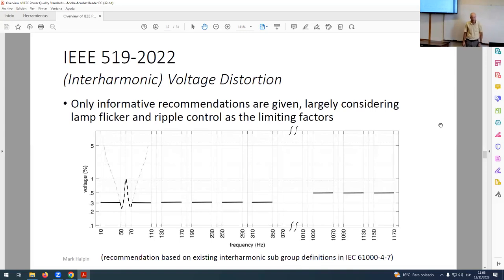What about interharmonics? Now, especially for my company in Alabama, we have 7 arc furnaces. Each one is 100 megawatts or more. Our furnaces are major producers of interharmonics. More and more in-use equipment also is producing interharmonics. A switching converter that is not switching synchronized to the power frequency will produce interharmonics. We still don't have limits for interharmonics in 519 that are what we call normal. They're not requirements yet, because interharmonics is a tough situation from a technical perspective.